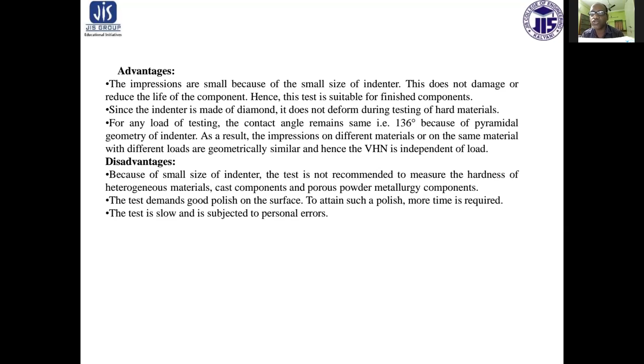The disadvantages are that because of the small size of the indenter, the test is not recommended to measure the hardness of heterogeneous material, cast components, and porous powder metallurgy components. The test demands a good polish on the surface. To attain such a polish, more time is required. The test is slow and subject to personal errors.